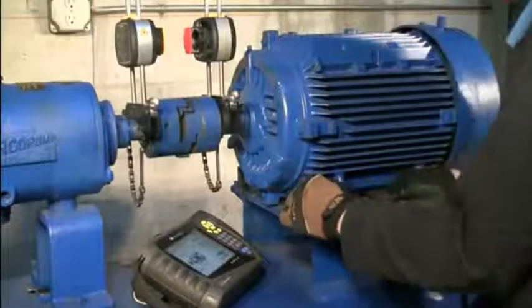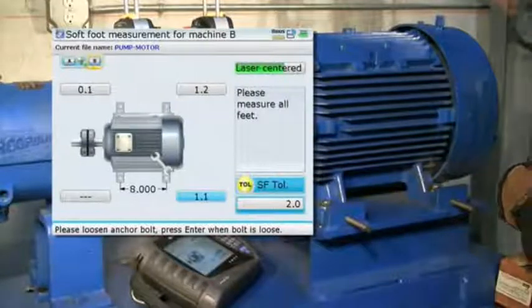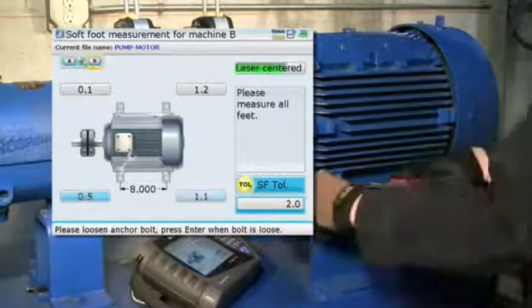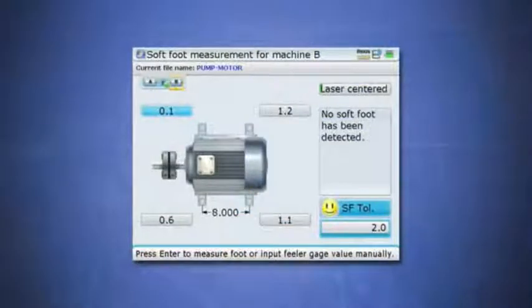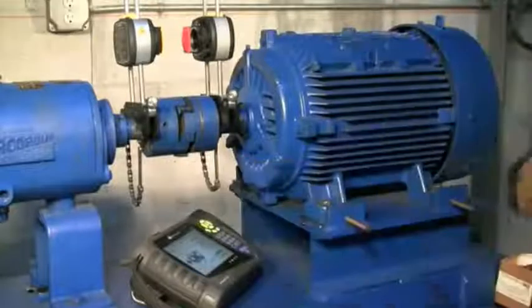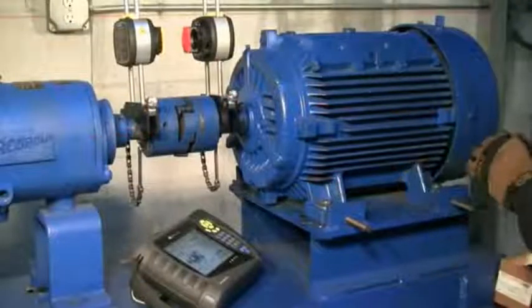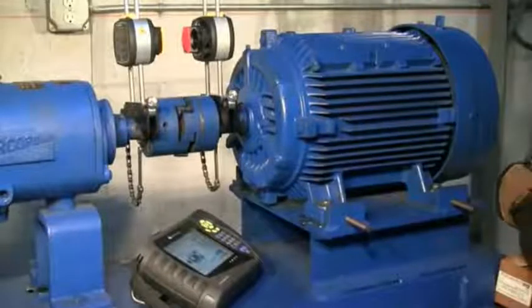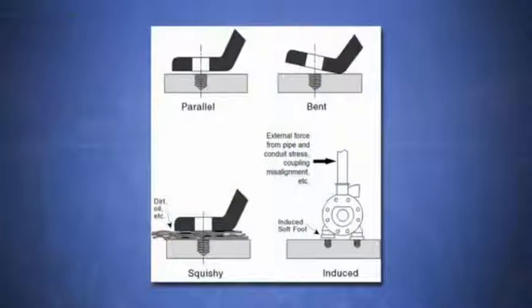Let's now begin our final softfoot check. Simply loosen one hold down bolt with the other three feet tight and let the Rotalign Ultra measure the shaft deflection, then retighten the bolt. Move to the next bolt and repeat this process for the remaining bolts. The numbers displayed are the calculated values for the shaft movement at each hold down bolt position. If your displayed values are less than two mils, you have no significant softfoot and can proceed with the alignment. If values are greater than two mils, that softfoot needs to be addressed. Be aware that the numbers are not necessarily the actual gaps under the machine feet — we are measuring the effect of that particular foot on the shaft deflection, not the actual gap. If softfoot was detected, measure the true gap under those feet using a feeler gauge to determine the exact softfoot condition, such as a parallel air gap, bent foot, or deflecting base.